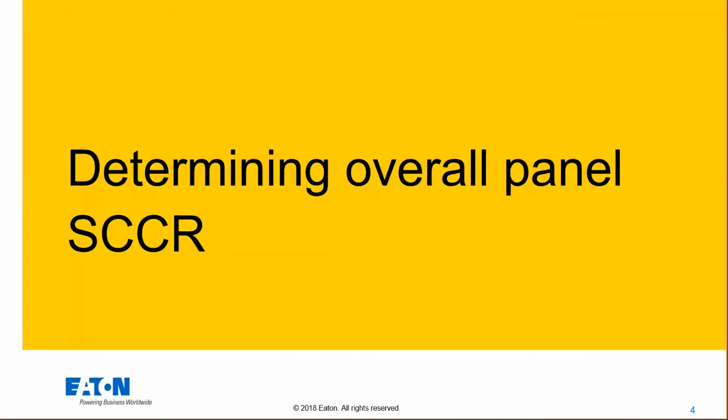So you don't have to use it, but what it does is it helps raise the overall rating of your panel. Because if that contactor remains at 5,000 amps, then the rating of your panel is 5,000 amps. You don't have to, but the point today is that most of the time, 5,000 amps is not going to cut it for industrial control panels. At the end of this presentation, I'll show you some new stuff in the NEC that came up in 2017. We're not there yet in Pennsylvania, but for people on this call shipping out of state and to other parts of the country, you're certainly going to want to understand how the NEC works when labeling panels.